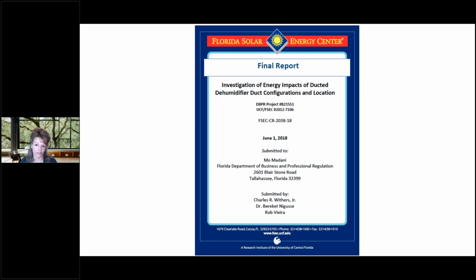But it heats up the coils of the AC system, which means that we get less latent removal from our air conditioner. And we're counting on that air conditioner when it's running to remove moisture. And then when that AC system shuts off and the dehumidifier comes on, it blows all that water back into the house. And that's what typically is happening when I get those calls. So go in, put it on the supply side, tie in the supply side, and everything works. So we do not want to tie in on that return side. Now you'll see it in our manuals. We understand sometimes that's the only way, but that is our least recommended of all of our installs. And we do share all those cautions that you need to understand if you're going to do it that way.